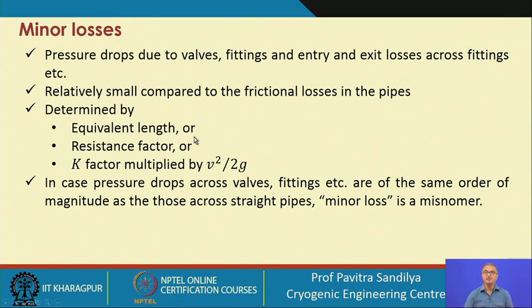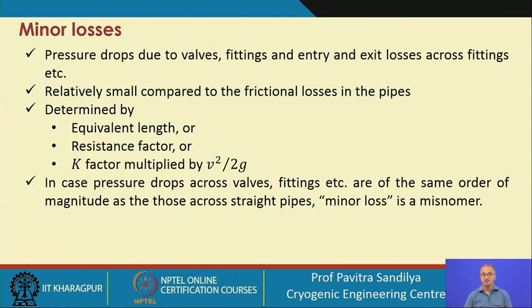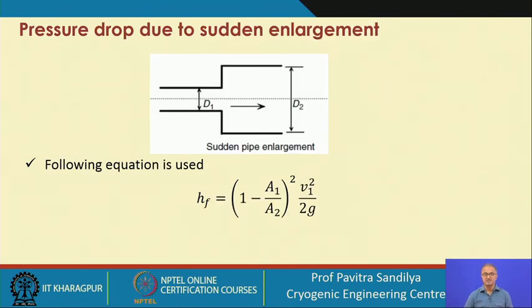The total pressure drop offered by these fittings and valves does not generally match the pressure drop across the whole straight pipeline. Minor losses may be determined using equivalent length, resistance factor, or K-factor methods. Sometimes the total pressure drop from fittings and valves may equal or exceed the major losses — in that case, calling them 'minor' losses is a misnomer, but the name sticks.